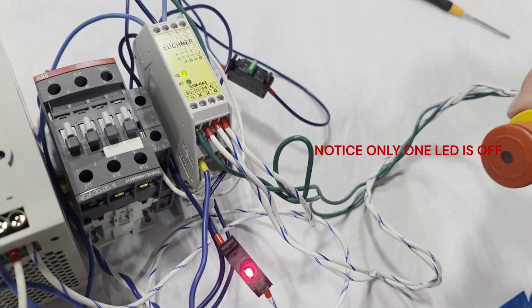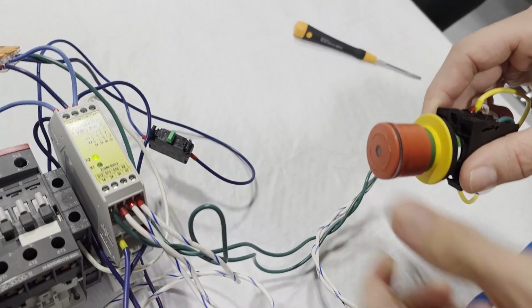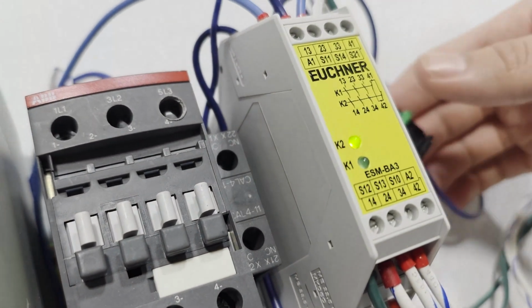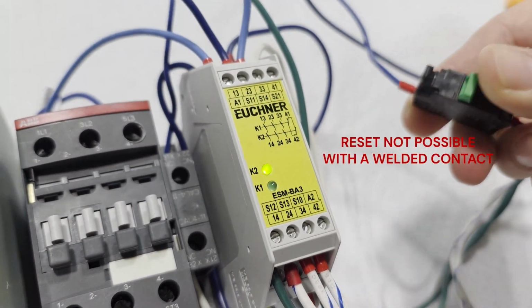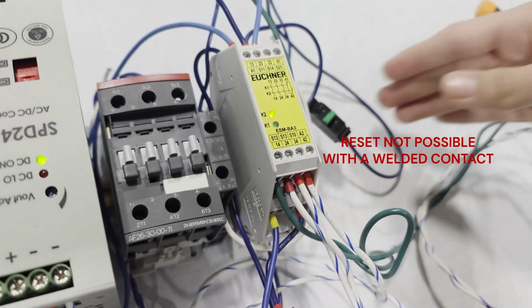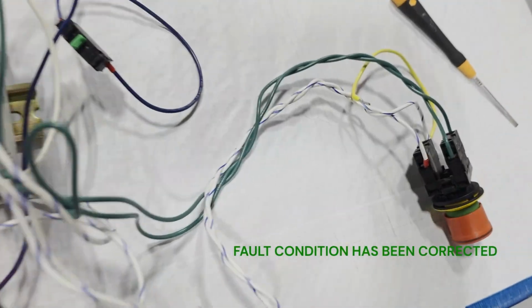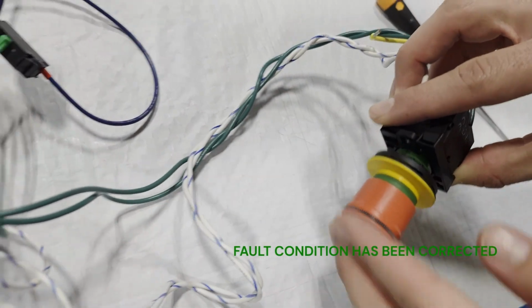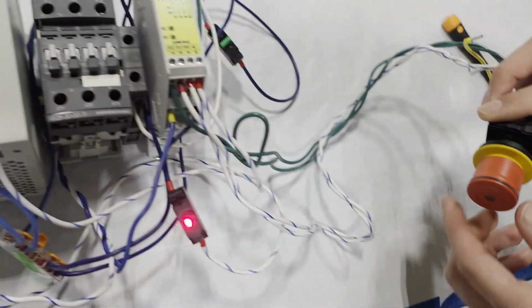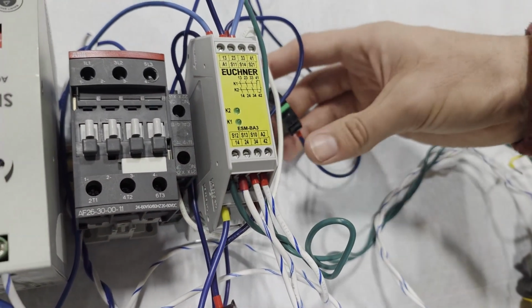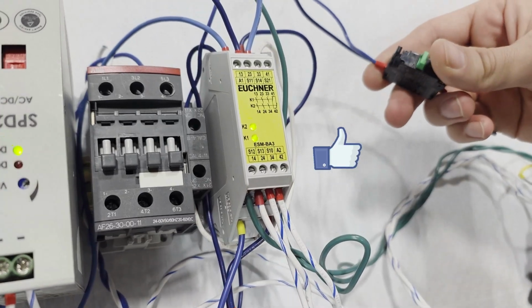Now we should not be able to reset until the problem is fixed. That doesn't reset it. So we are still in a safe state. Okay, so the short circuit has been resolved, or the welded circuit has been fixed. And it's reset. And now we are back to operation.